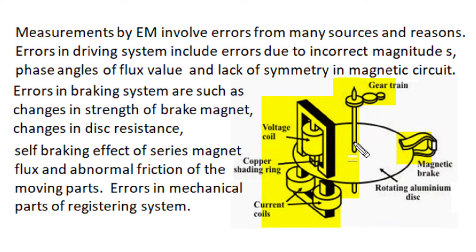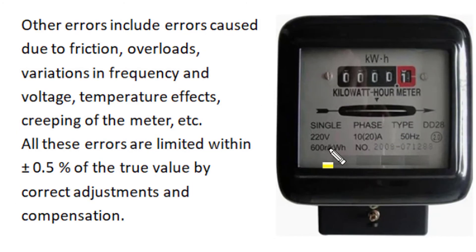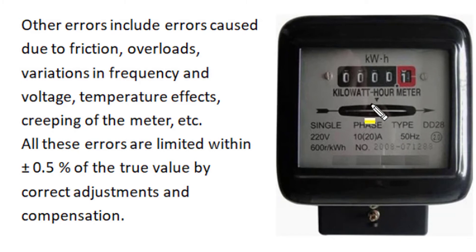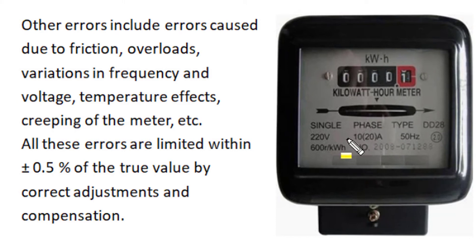Friction in all moving parts is a non-linear parameter and abnormally high friction is a serious concern for accurate energy measurement. Mechanical adjustment and gear trains of the register and counting mechanism can also cause error. The energy meter must work across a wide range of load conditions — sometimes overloaded, often underloaded — with wide variation in operating power factor. Error may be caused by friction, variation in frequency, voltage, temperature, and overload. Correct adjustment is required to maintain accuracy within ±0.5 percent.